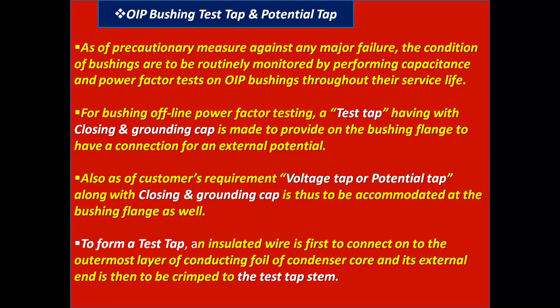For bushing offline power factor testing, a test tap with a closing and grounding cap is provided on the bushing flange to allow a connection for an external potential. Also, as per customer requirement, a voltage tap or potential tap along with a closing and grounding cap is to be accommodated at the bushing flange as well.